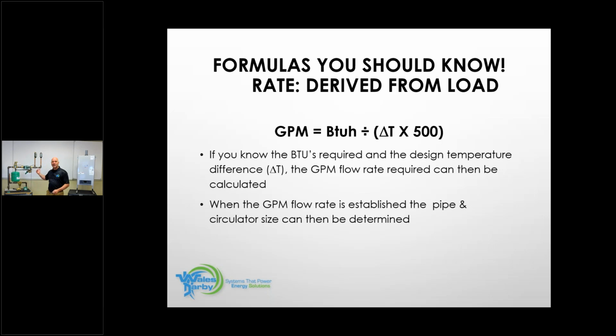This is a boiler system. Every gallon of water that leaves has to come back. The BTU that leaves has to come back. It's going to be BTU just at a cooler temperature. This is not like a hot air system where as I have takeoffs coming off of my ductwork, I can then slowly reduce my ductwork. Whatever header comes out of here, I need the same size header on my return because the same amount of BTU is coming back. It's just coming back at a lower temperature. So it's all about flow in a hydronic system. That answered the question, hopefully? Oh, yeah. Yeah. Great.